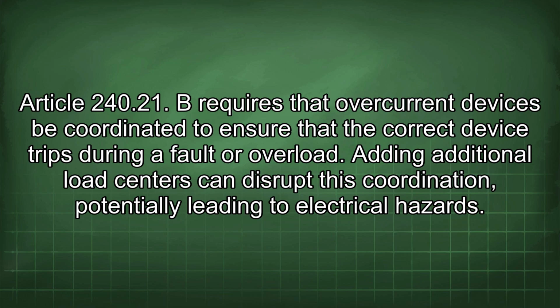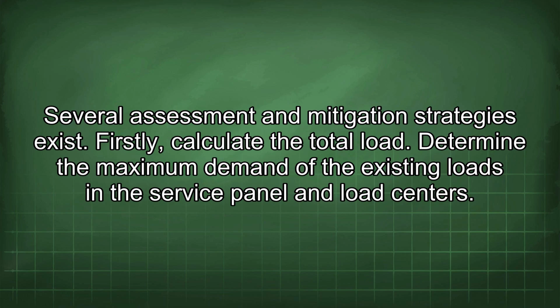Article 240.21 B requires that overcurrent devices be coordinated to ensure that the correct device trips during a fault or overload. Adding additional load centers can disrupt this coordination, potentially leading to electrical hazards. Several assessment and mitigation strategies exist.